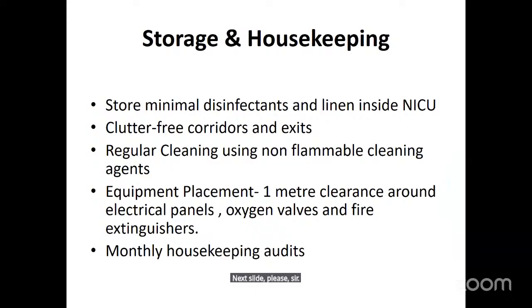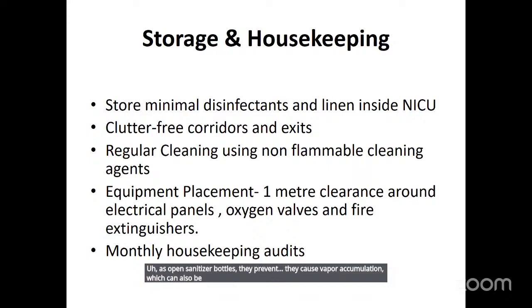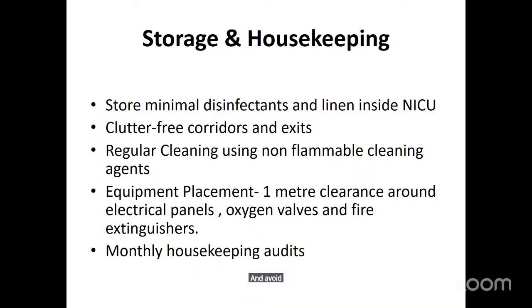So there should be a minimal storage of disinfectants and linen inside NICU. They should never be stored in bulk. Only the minimum required quantity should be kept at bedside. And all sanitizer bottles must be tightly capped when not in use, as open sanitizer bottles cause vapor accumulation, which can also be a cause of fire. And avoid placing sanitizers near electrical outlets, radiant warmers, or oxygen outlets.